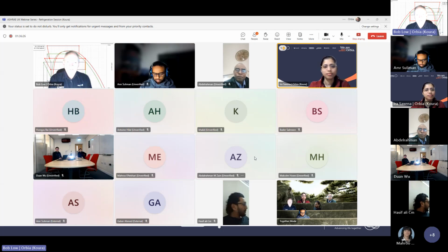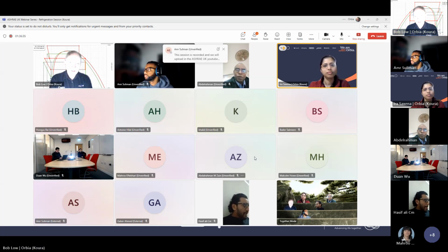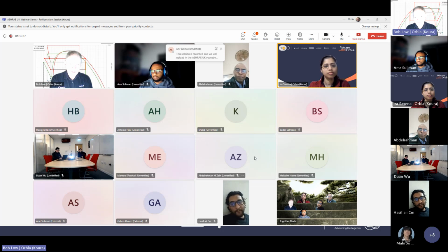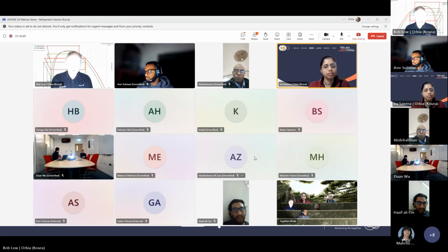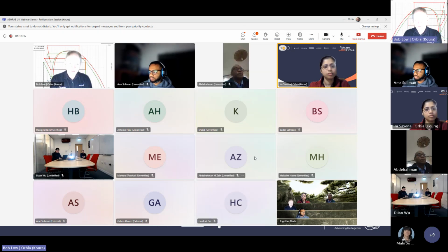Yeah, I think we basically try to be honest with people. A good example is the supermarket refrigeration sector. People want A1 refrigerants for their traditional supermarket designs because the refrigerant goes out to the store, there's a potential for loss of refrigerant into the store, and the store is not designed for flammable, so it needs to be non-flammable. That's fine. But then they want GWP less than 750. Okay, non-flammable fluids can be designed for 750, and then they want no temperature glide, and then they want the same performance as 404A. And at that point, we have to have the gentle but frank conversation that you can't have everything.